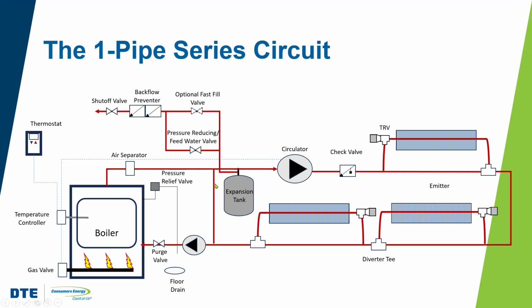Now, in the drawing here, this is just for visual purposes, so the length of this piece of pipe here may seem to be longer than what it would typically be in practice. Typically, we would really want this to be, for a system like this, 6 inches or less, right? We want this to be a very short pipe here. We're just trying to hydraulically isolate this here so that we can have continuous flow around here, right? That allows us to achieve better comfort conditions in the home.